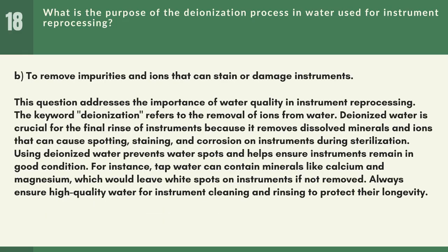Answer: B. To remove impurities and ions that can stain or damage instruments. This question addresses the importance of water quality in instrument reprocessing. The keyword deionization refers to the removal of ions from water. Deionized water is crucial for the final rinse of instruments because it removes dissolved minerals and ions that can cause spotting, staining, and corrosion on instruments during sterilization.